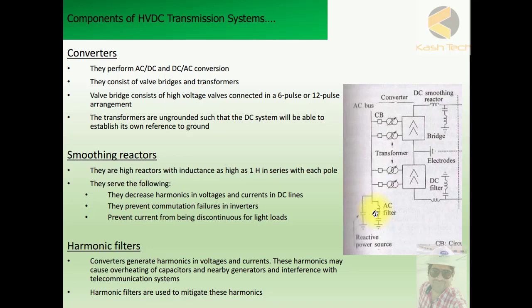The smoothing reactors can store energy, so they fill the ripples — similar to a capacitor in DC systems used to remove ripples and make the DC supply smooth. They also suppress transients and protect the communication network from transient surges. Additionally, they prevent current discontinuity for light loads by filling the gaps.